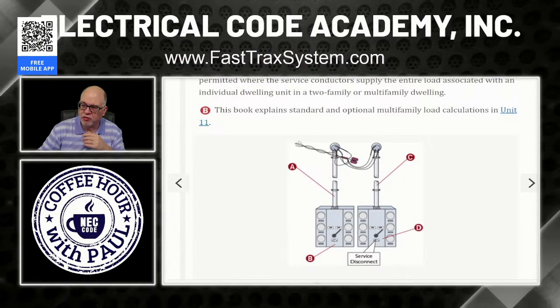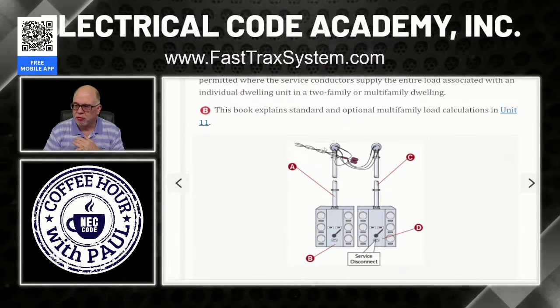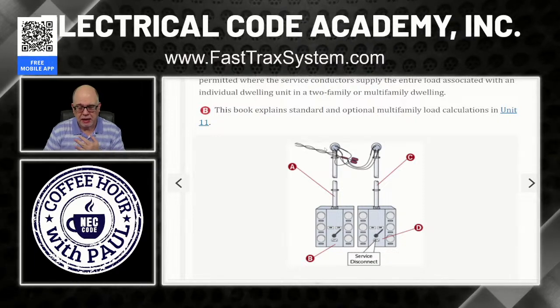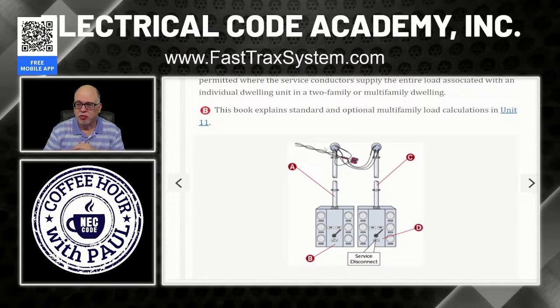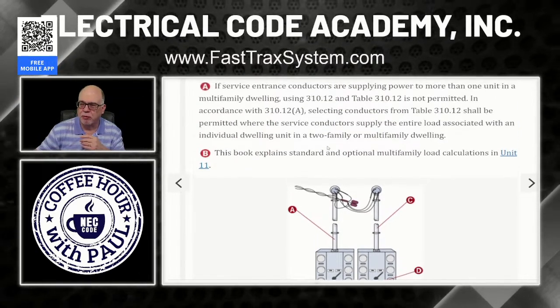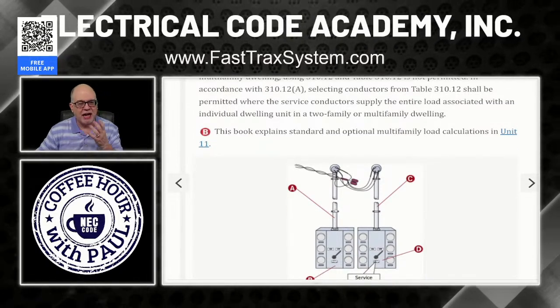And this is one service to a building, one drop, okay? So you can't use 310.12, but you're going to do a load calculation and you're going to size those conductors based on your load, right? That's what you're going to do. And that's traditionally what you would do anyway. So that's why we kind of get that 83% rule out of the way. In a multifamily like this, you're not going to be able to do that.